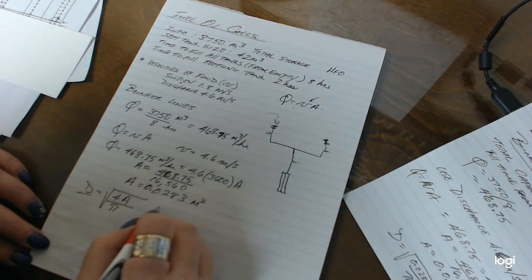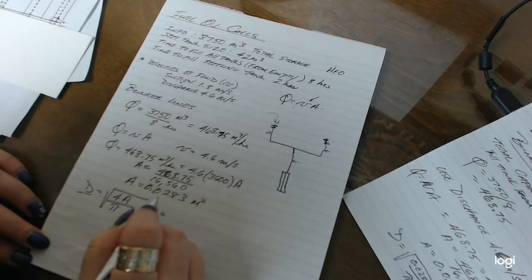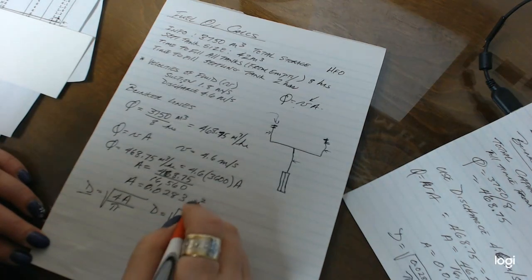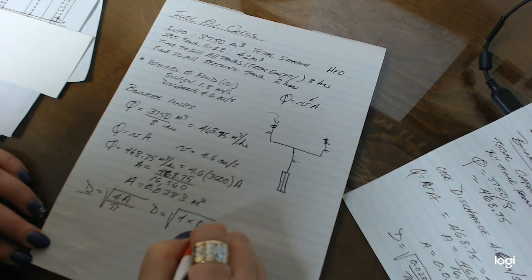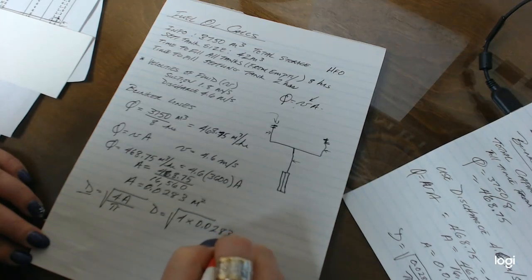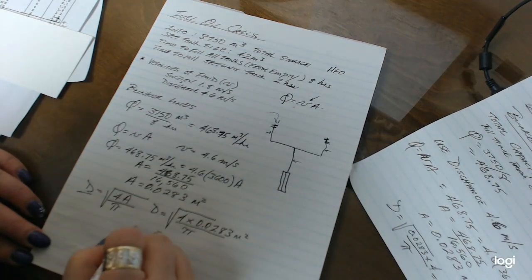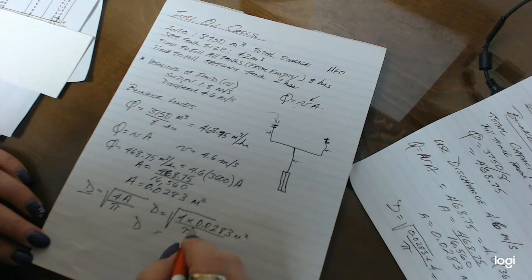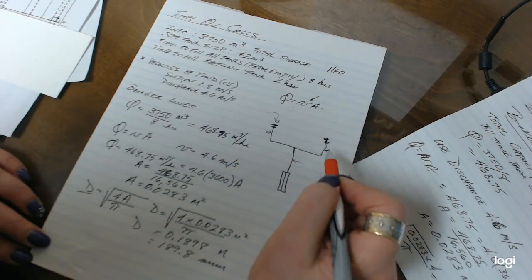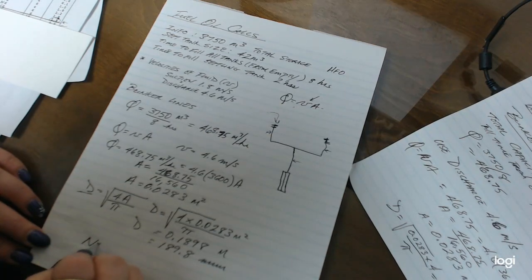So when I'm looking at this D, what I'm trying to calculate for now by putting the values in is that D in this case is going to be equal to 4 times 0.0283 meters squared, and I'm going to divide that by pi, and my answer that I'm going to get for D is going to be equal to 0.1898 meters, okay, which equates to 189.8 millimeters. Okay, so what I'm trying to look for now so I can size these pipes and put that on my diagrammatic is what is the nominal pipe size.